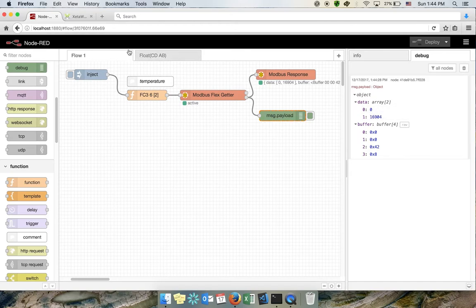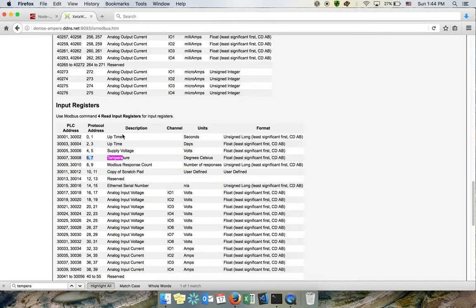I'll go back to the specification sheet and see that the format is specified. In this case it's a float divided into two 16-bit values making 32 bits total, with the most significant value coming first. You might wonder why this format exists — the Modbus protocol is quite old, probably more than 30 years old.